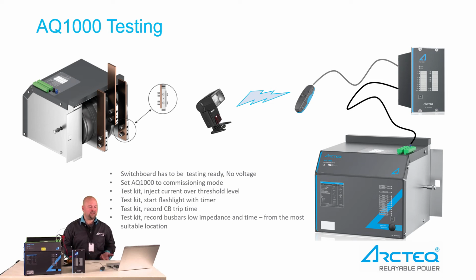Test kit, inject current over the threshold level. You can set the thresholds from the relay. Start the flashlight with a timer if necessary, or just manually like I'm going to do next. Record the circuit breaker tripping time. If the customer wants to know better timing, it is of course possible. It is possible to measure the low impedance state. It is possible to measure the circuit breaker opening time. And record the busbar low impedance and time from the most suitable location and a safe location, of course.